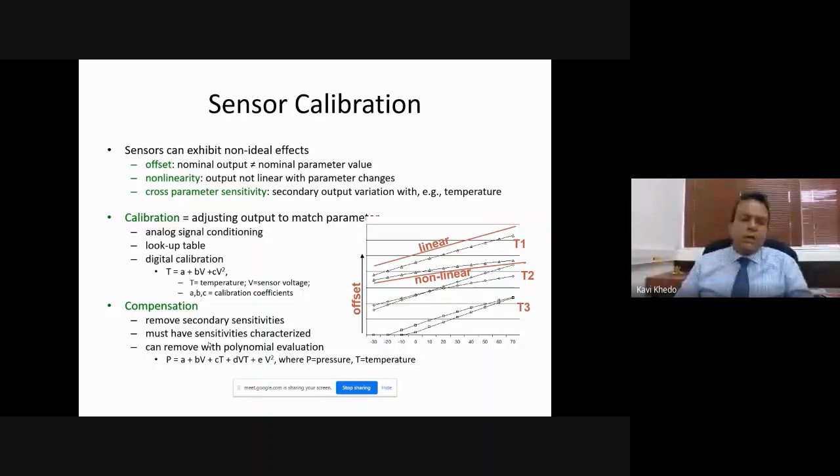When the water rises to a particular level, it should translate to some centimeter or meter value, normally through the voltage level. Very often, the water is increasing, but the voltage and value you get is not matching what it is supposed to give. Why? Because the sensitivity of the sensing element has changed slightly. When sensors are manufactured, put in boxes and shipped to us, there can be slight variation in their sensing element. When exposed to high temperature or pressure, the sensing element sometimes gets distorted.